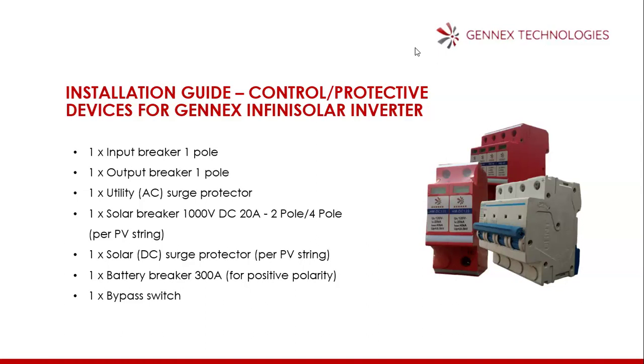So one battery breaker, which is about 300 amps for positive polarity of the battery. Then one bypass switch, which is a 3-pole or 3-phase bypass switch, so that when there is a problem with the inverter, you can easily bypass to direct.